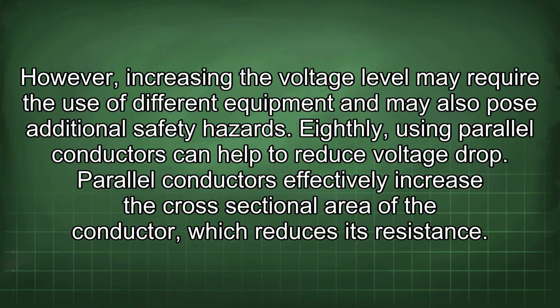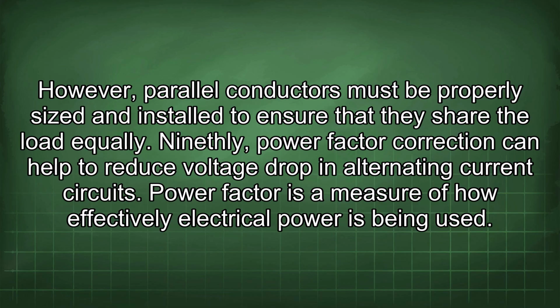Eighthly, using parallel conductors can help to reduce voltage drop. Parallel conductors effectively increase the cross-sectional area of the conductor, which reduces its resistance. However, parallel conductors must be properly sized and installed to ensure that they share the load equally.